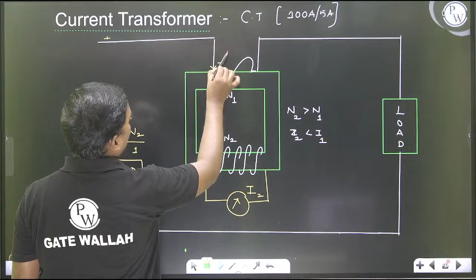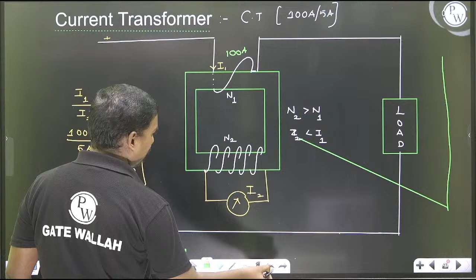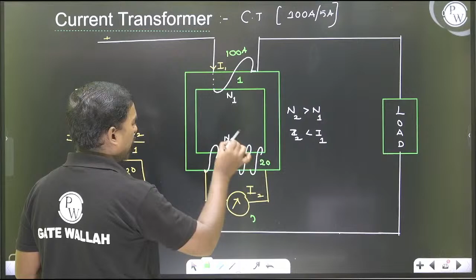In a current transformer, it is again a combination of a transformer and an instrument, but here the transformer comes in series with the current. This higher current, generally 100 amperes, has to be converted to 5 amperes. So the number of turns at the secondary side must be greater. I am choosing the number of turns at the secondary as 20, and the primary as 1 turn, so that I get I2 as lesser.